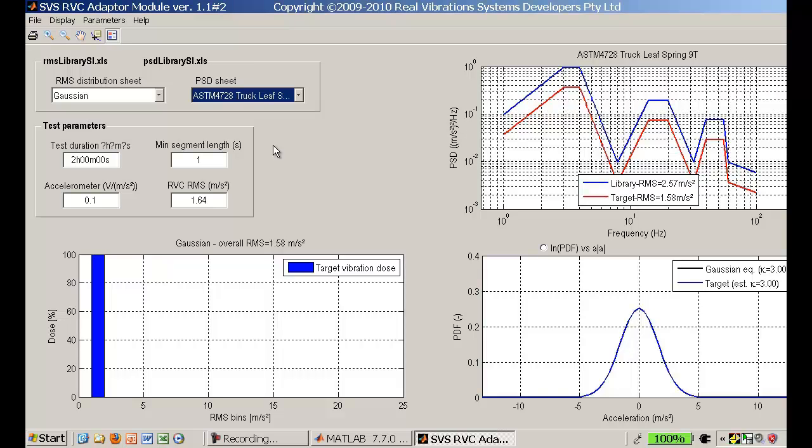When using ordinary random vibration controllers, the only other variable that can be configured is the RMS level that remains constant throughout the test. This approach is very limited and does not produce realistic vibrations. With the statistical vibration synthesizer, some reasoning can be applied to produce non-stationary random vibrations by defining a range of RMS vibration levels to be simulated.